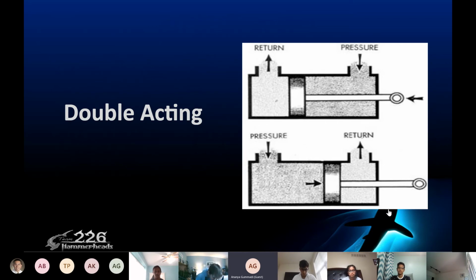And something important to note is that you must apply power for a period of time, maybe around 0.05 seconds, to allow time for the physical valve or the slider to move to change the setting. So after moving the valve, you can turn off the solenoid power or remove pressure because the valve will stay in the new position.